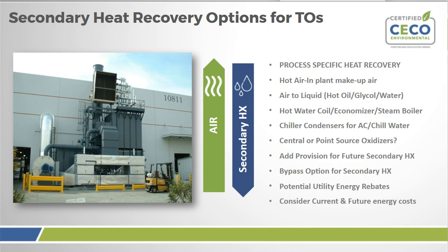Some customers may think that they will need a future secondary heat exchanger. We can design a provision in there. I think most RTOs can be designed for that, to have a spool piece or whatever. And also, if you need to bypass the secondary heat exchanger, a lot of times you may not need all that heat for in-plant heating on air-to-air in the winter, so you can bypass that. So you need to think of all those things to design into your secondary heat recovery section and module.